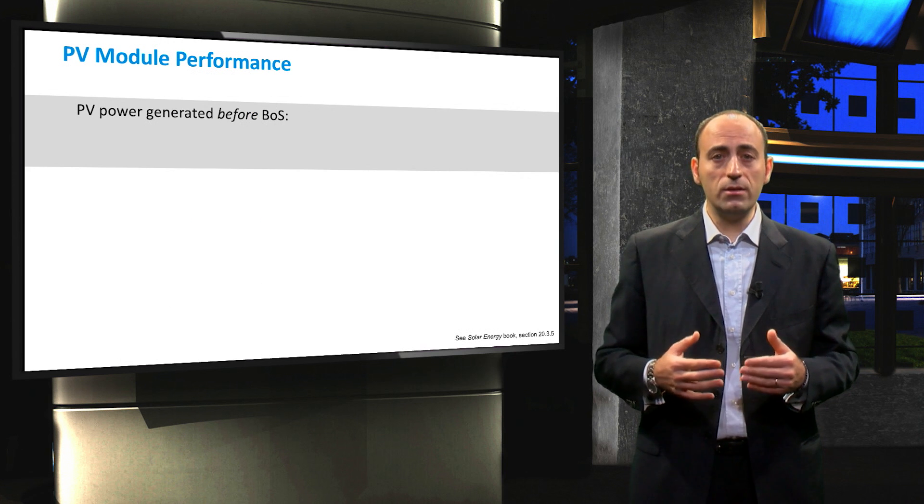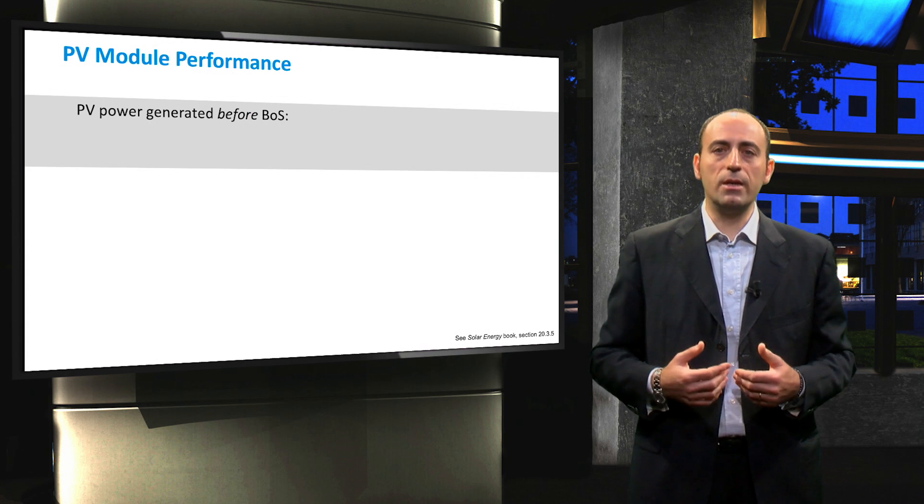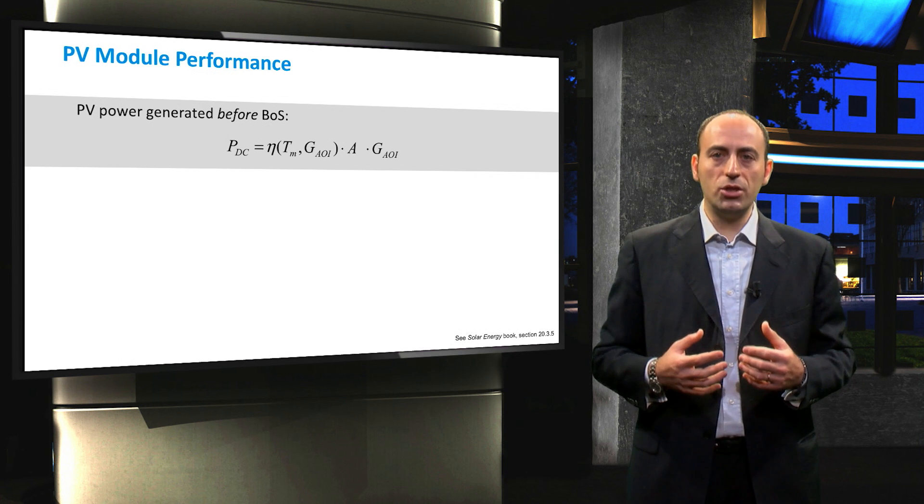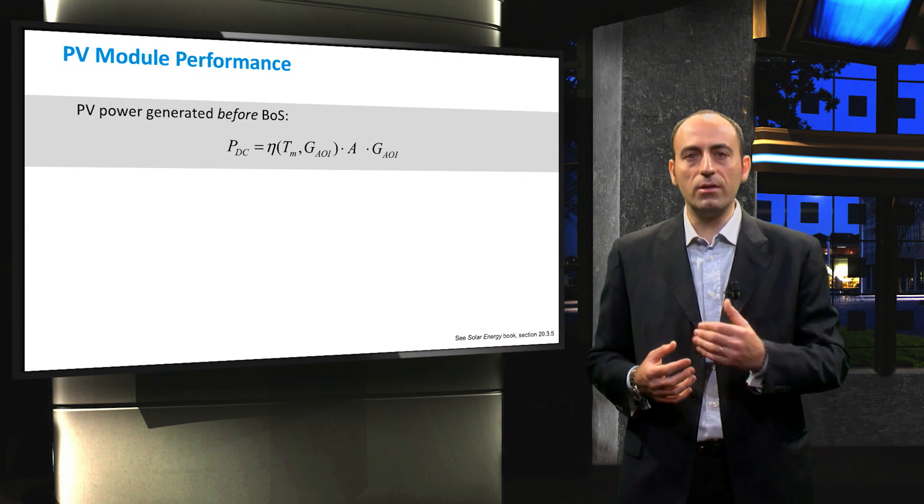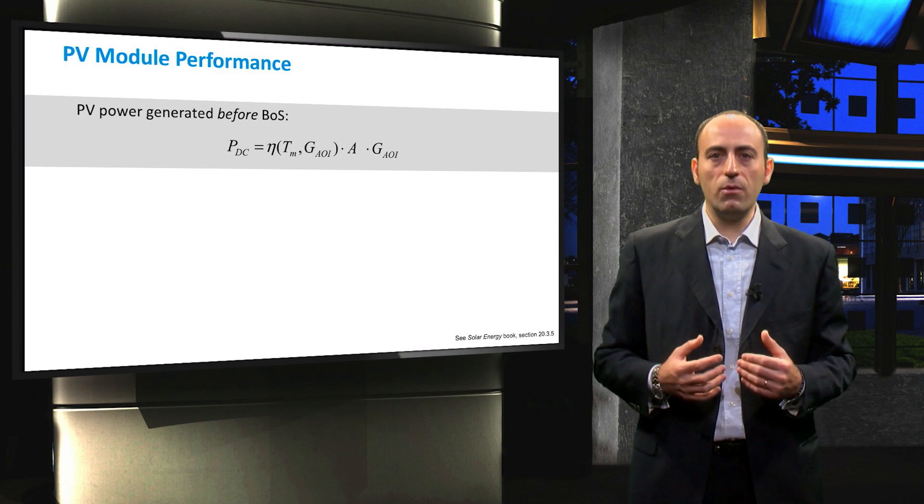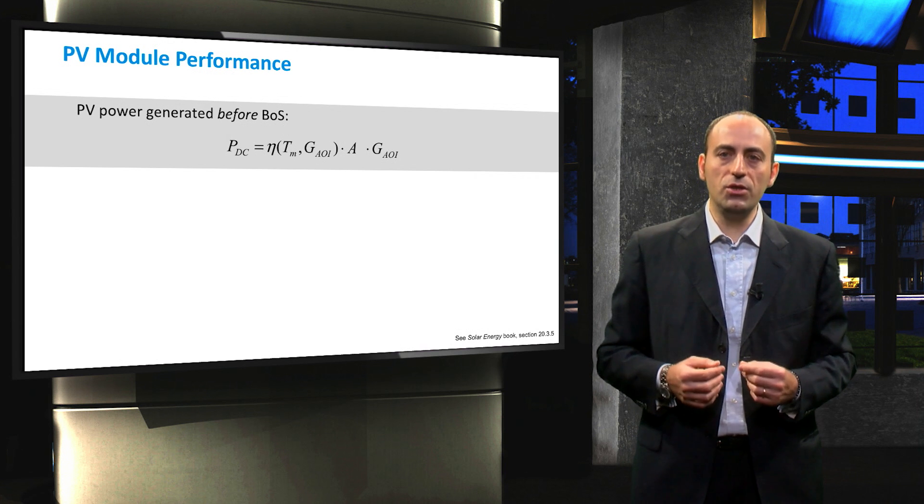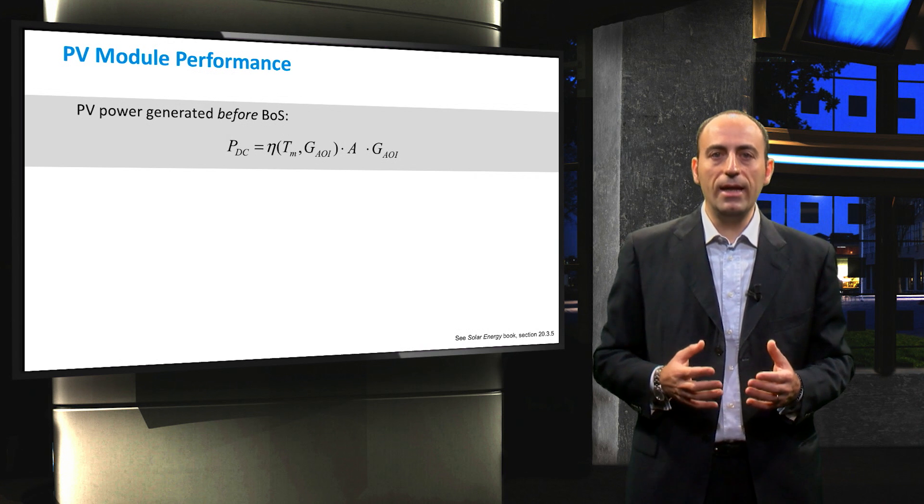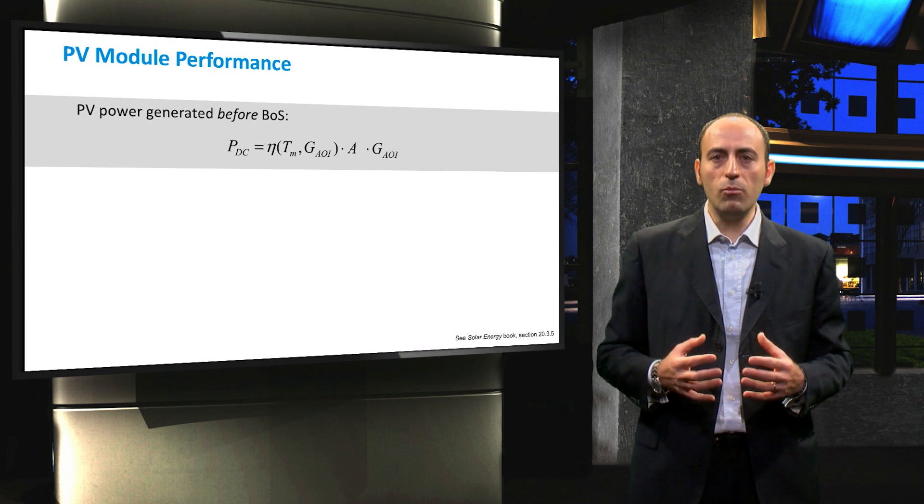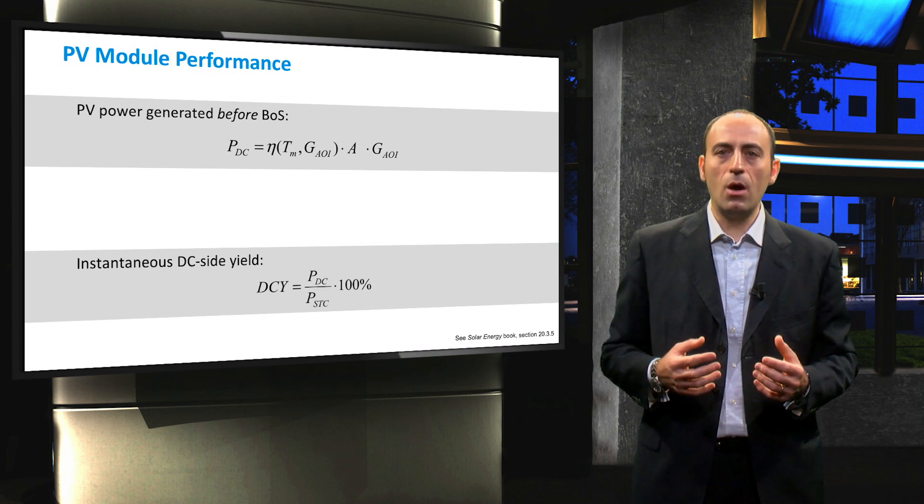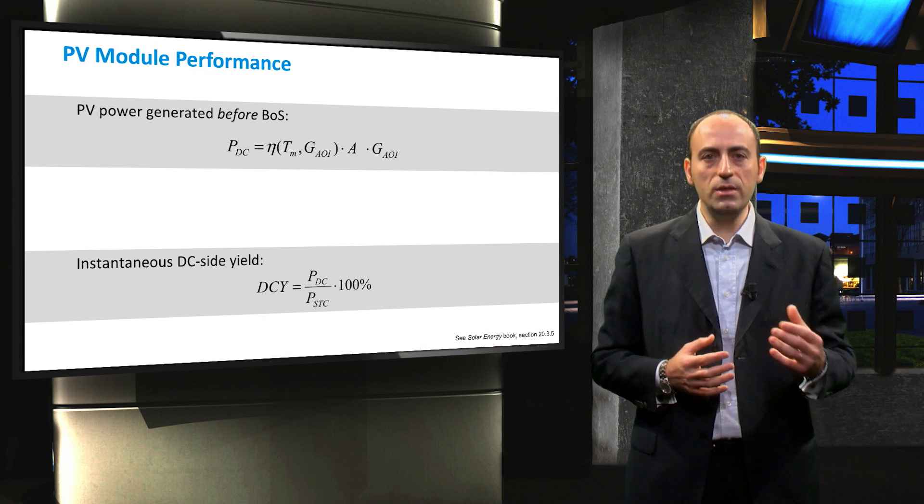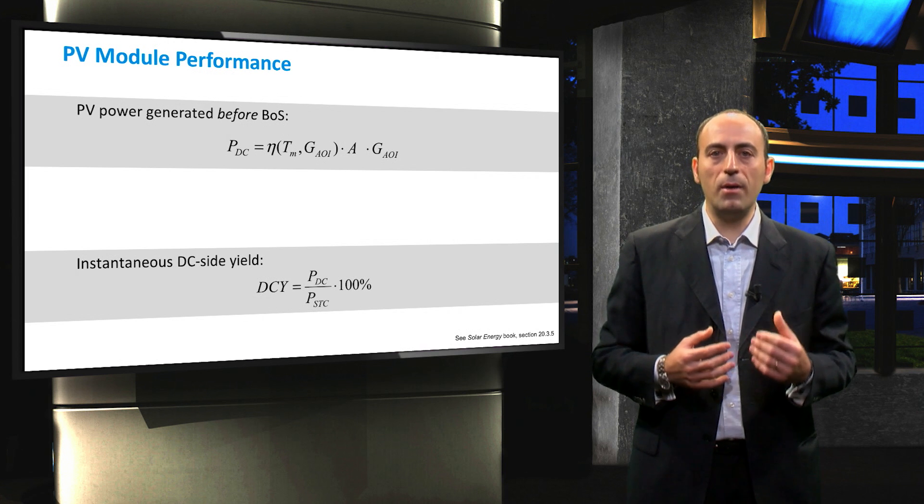As the goal here is to obtain the PV side performance in terms of DC side yield and to show you how to compute it, we need the DC side power generated by the PV panels before entering the balance of the system that basically is the charge controller or the inverter. The power generated is a function of the efficiency of the module, which we just calculated, and it is also a function of the panels area and incident irradiance. What will come out from this formula is just power in watts. So now we can define the instantaneous DC side yield as the ratio between the DC power generated divided by the power at STC, which is the one stated in the datasheet.